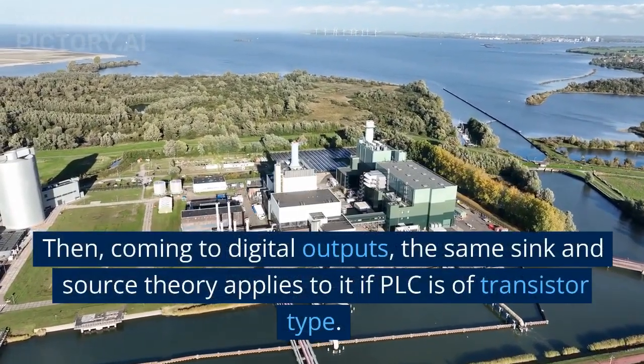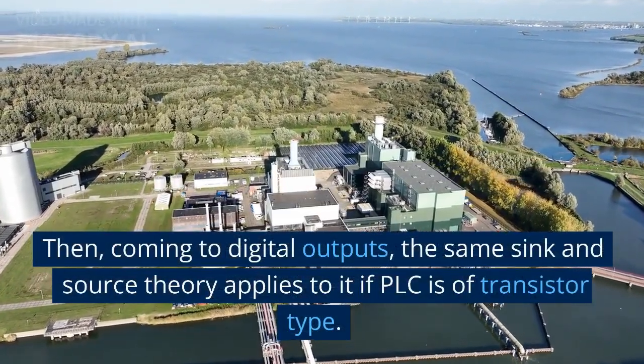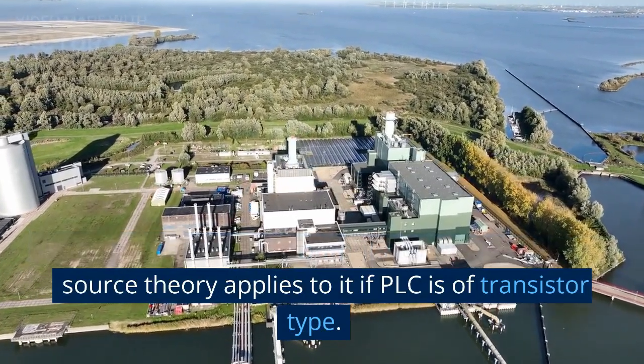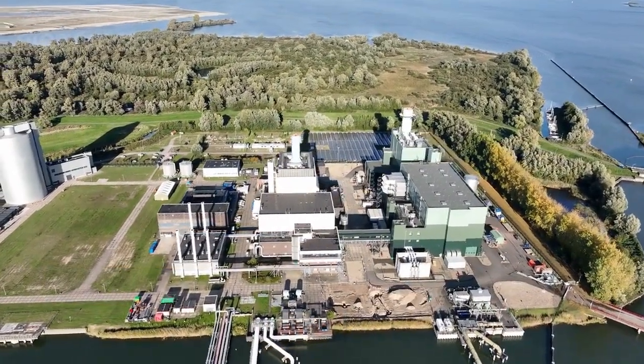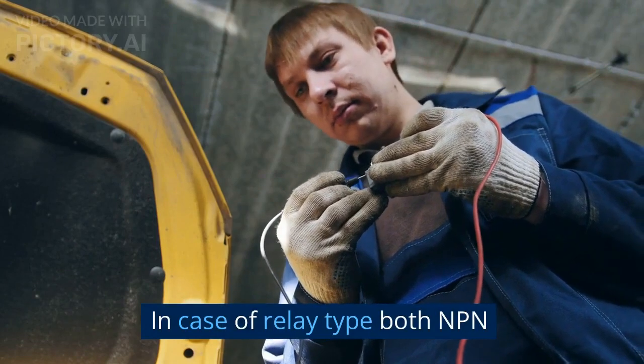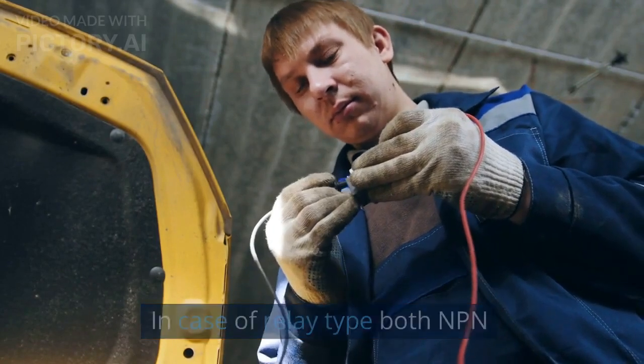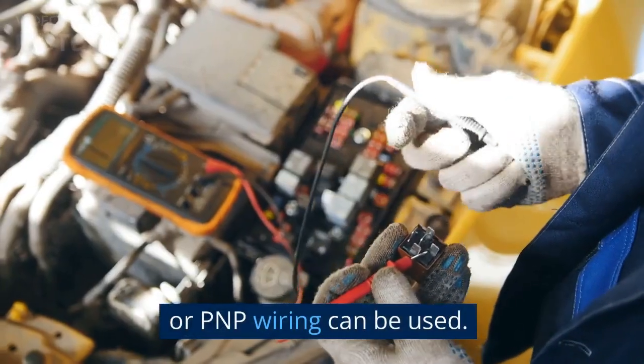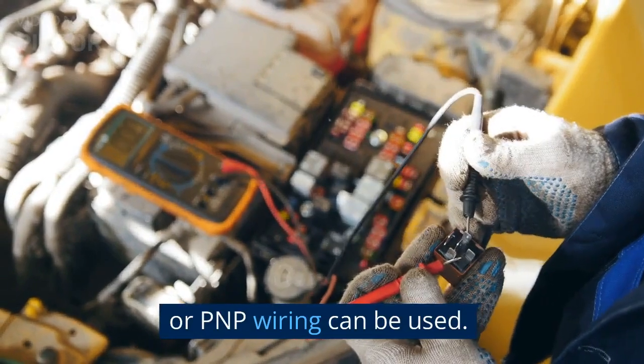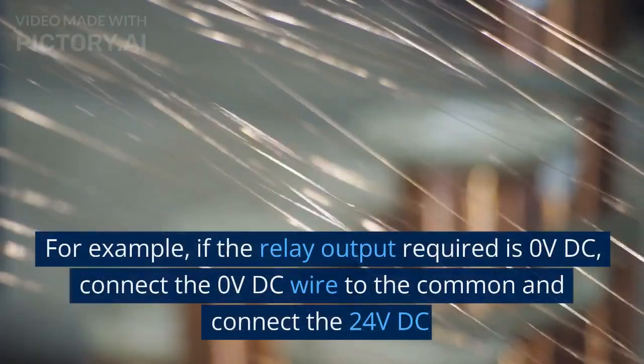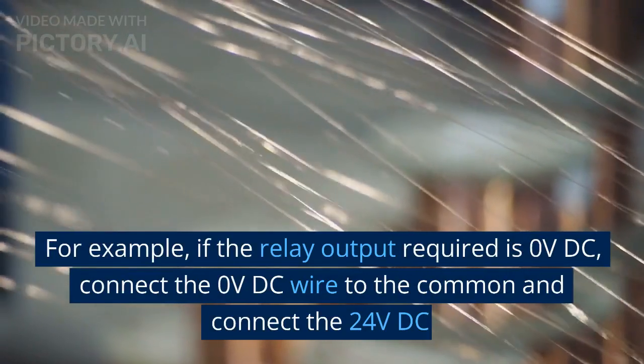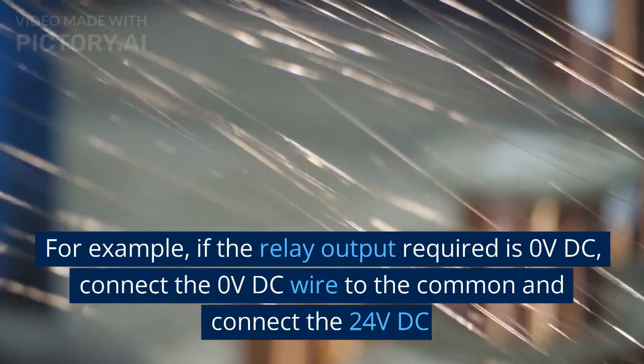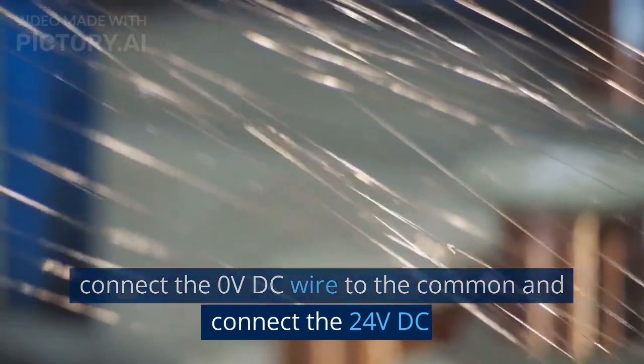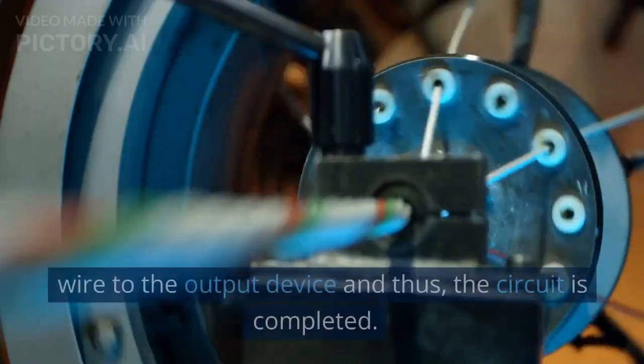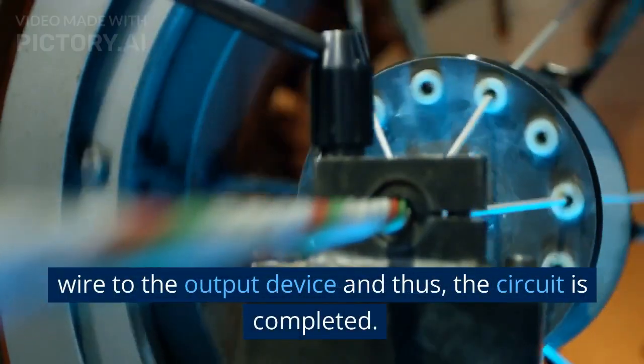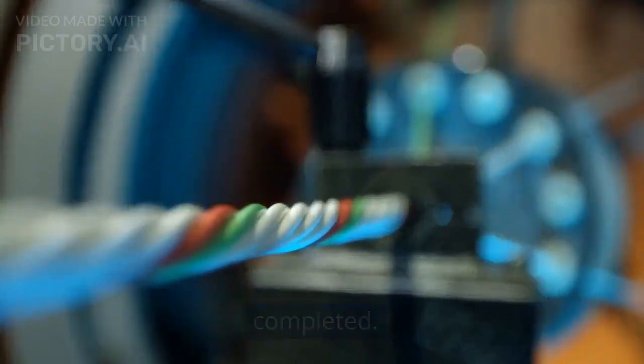Then, coming to digital outputs, the same sink and source theory applies if the PLC is of transistor type. In case of relay type, both NPN or PNP wiring can be used at the output terminal. For example, if the relay output required is 0 volts DC, connect the 0 volts DC wire to the common and connect the 24 volts DC wire to the output device, and thus the circuit is completed.